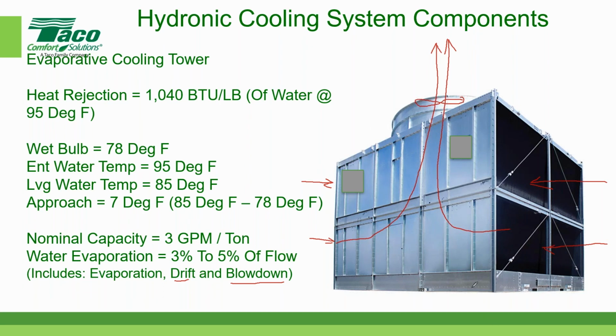And so what you do periodically is you open a valve. There's a valve at the bottom of the tower. Typically that goes to a drain somewhere. And usually it has to go to a sanitary system and not storm drains, because there are chemicals in there. You can open the valve manually, but most people use automatic valves. They open up based on the conductivity of the fluid. The more the fluid conducts electricity, the dirtier the fluid is. And so they open the valve electrically and then blow it down.